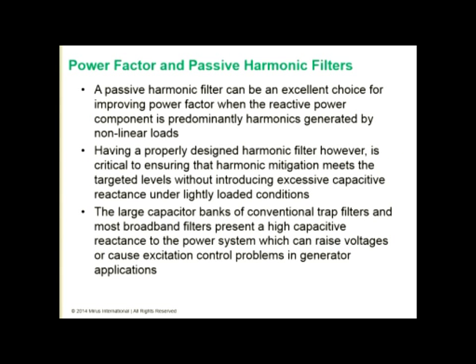So let's take a second and look at passive harmonic filters and power factor. If we have high levels of distortion reactive power, then the only way to improve the power factor is to remove the harmonics. And one method of doing that is through passive harmonic filters. Having a properly designed harmonic filter, however, is critical to ensuring that harmonic mitigation meets the targeted levels without introducing excessive capacitive reactance under lightly loaded conditions. The large capacitor banks of conventional trap filters and most broadband filters present a high capacitive reactance to the power system, which can raise voltages or cause excitation control problems in generators.